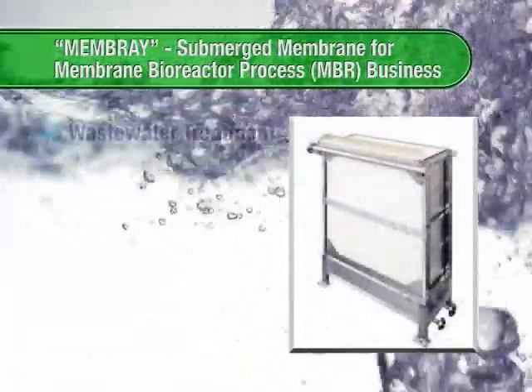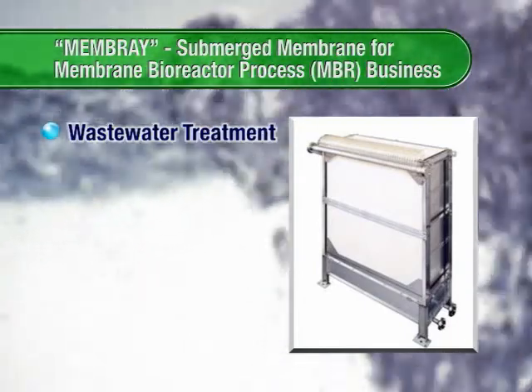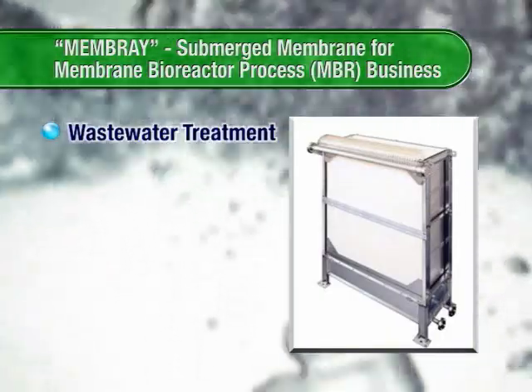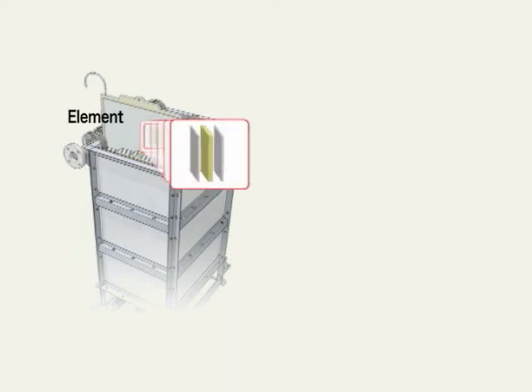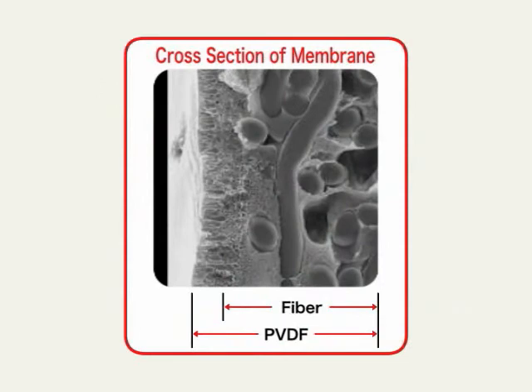In the field of biological wastewater treatment, the gravity sedimentation system for solid-liquid separation in the conventional activated sludge method can be replaced with a membrane filtration system, MBR, or membrane bioreactor. The MBR membrane module contains 100 to 200 flat panels with flat sheet membranes attached on both sides. The flat sheet membrane is made of PVDF, polyvinylidene fluoride, material which features excellent chemical stability and physical strength, as well as a narrow pore size distribution of numerous micro pores.